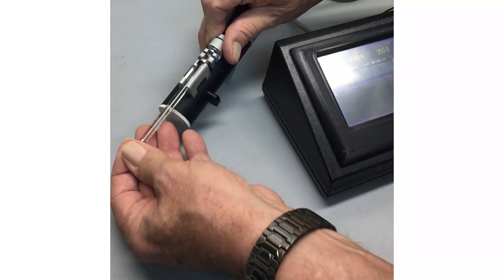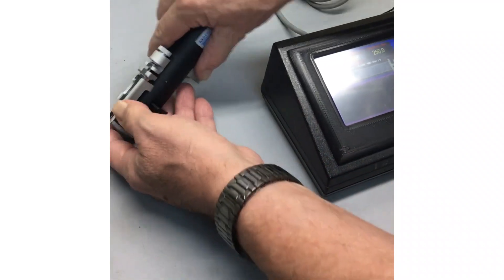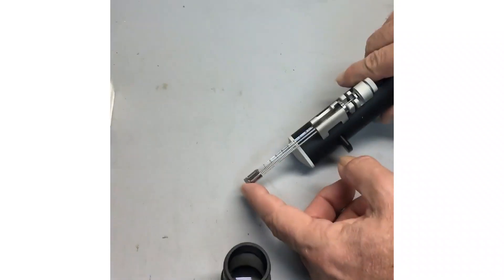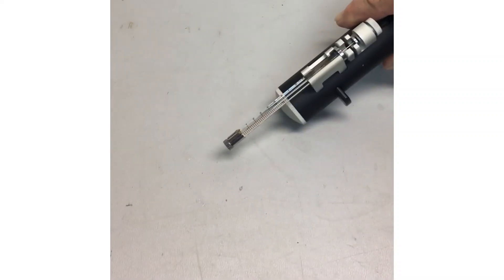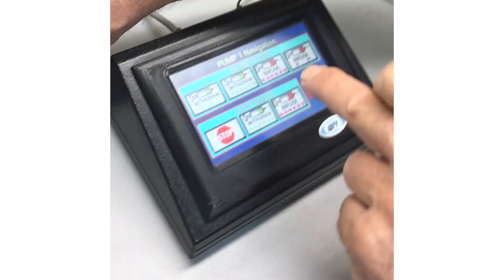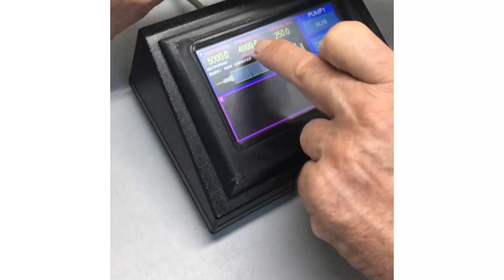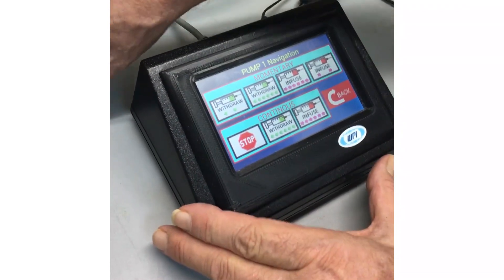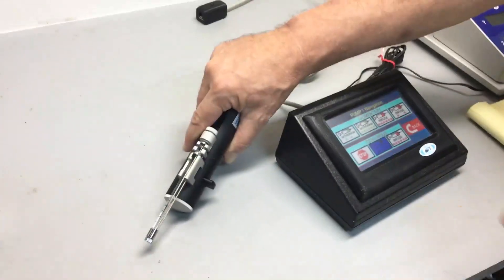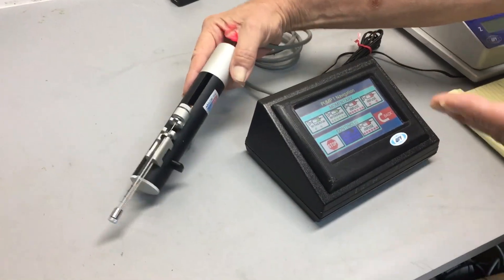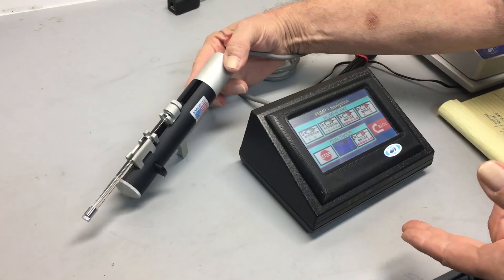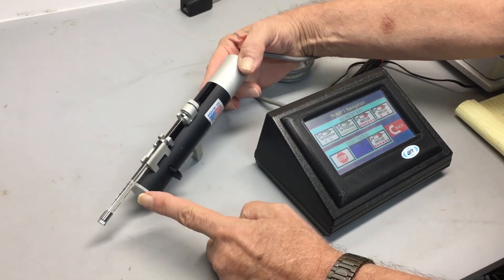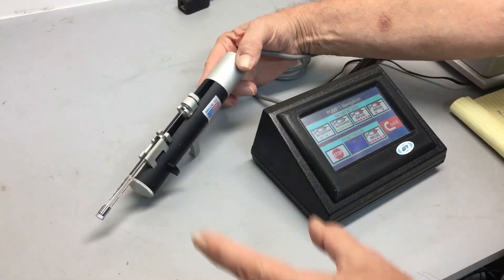I've actually pushed fluid all the way through the needle. This is nice and tight on here. Now I can stick this in my solution — let's say with the 26-gauge filling needle. I'm going to press and hold this screen. Now I'm on the navigation page. I stick the needle in my filling solution and push continuous withdraw. Now it's going to fill the syringe to the full 10 microliter mark with my drug or chemical. And I've got no air bubbles in here — it's a practical method for setting up the syringe.